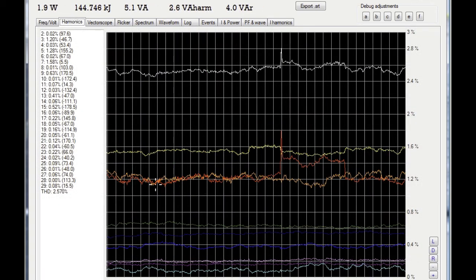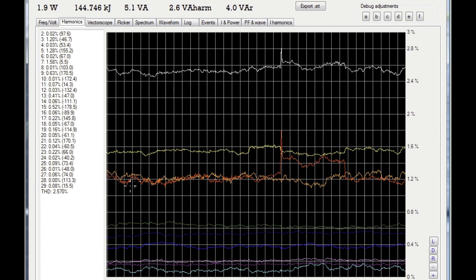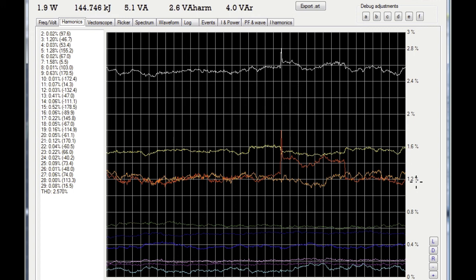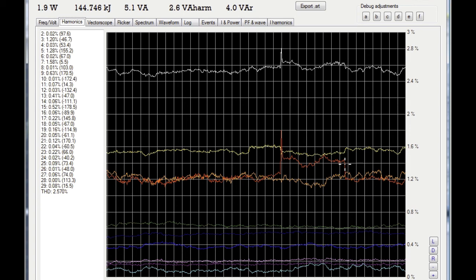We can actually see this on this numerical analysis here. We'll look at the red trace, because that's the one of interest. This measures the third harmonic distortion. This measures the amount of 150 Hz current, or voltage in this case. This is the voltage waveform we're looking at. The amount of 150 Hz voltage present. It hovers around at about 1.2%. In other words, of this 230 V AC, about 2.5 V is at 150 Hz distortion. When we turn the vacuum cleaner on, that jumps up a little bit. It jumps up to about 1.5%. That's simply a reflection of the fact that the vacuum cleaner is pulling the tops of the voltage waveform down further. And that is reflected in this higher distortion value.